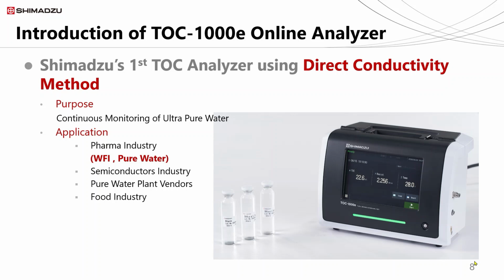Online monitoring is very important. Online sample is passing through continuously and any problem should be detected and necessary action should be taken immediately. Because if any problem occurs on the pure water or WFI line, it may cause a cost to the company. So, online water should be observed 24 hours frequently against any unwanted TOC levels.